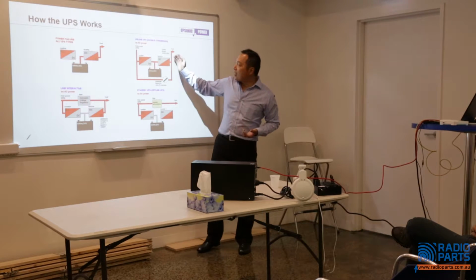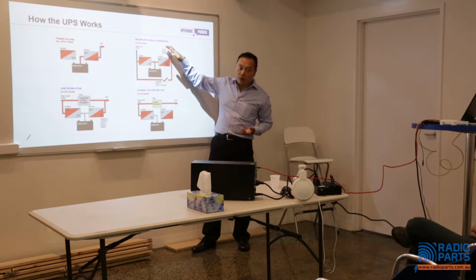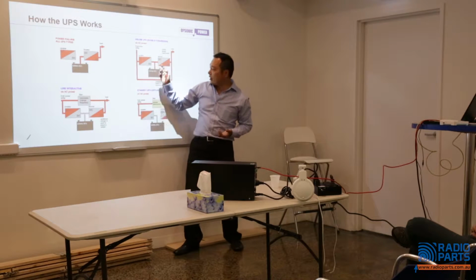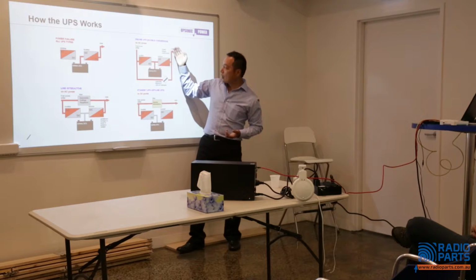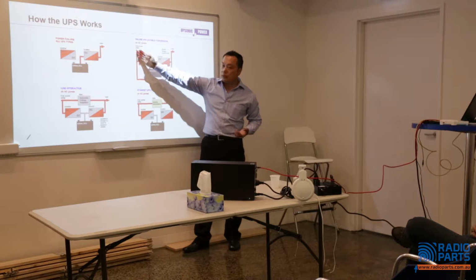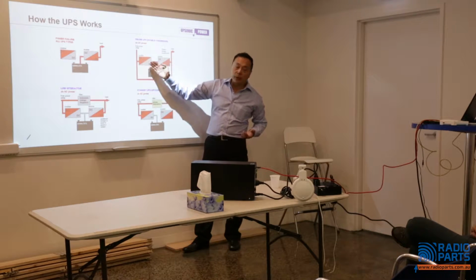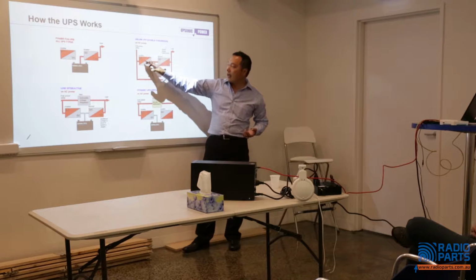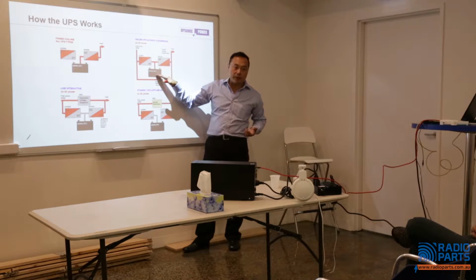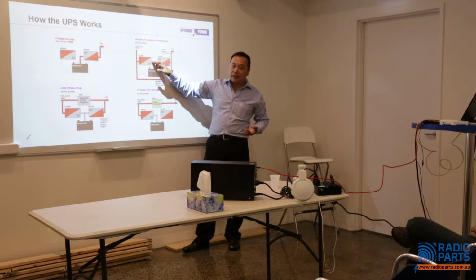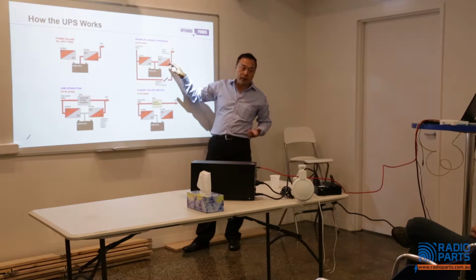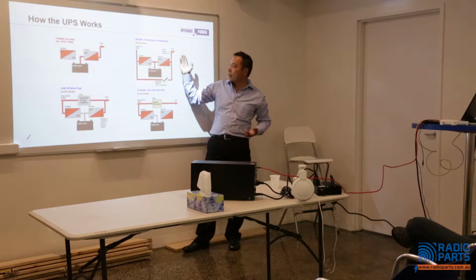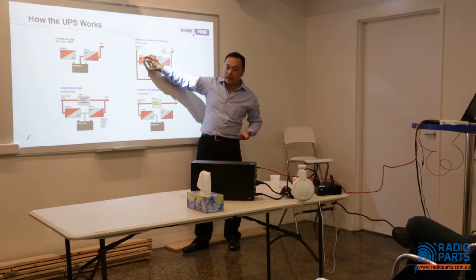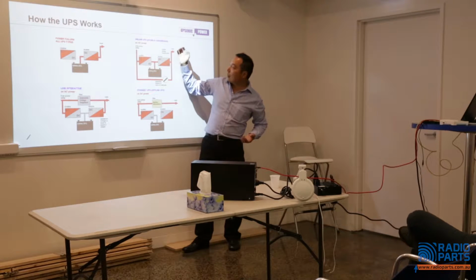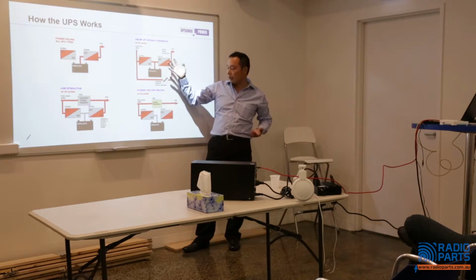The higher-end model is the online UPS, double conversion. It's different because there is no AVR. When input comes in, it goes through a rectifier, turning AC to DC, and charges the battery. At the same time, this DC power goes through an inverter, which converts the DC power to AC power. So it converts once, converts twice - that's double conversion, true online UPS.